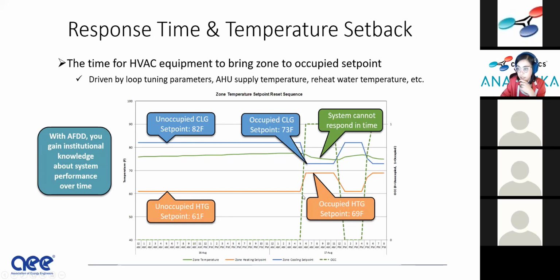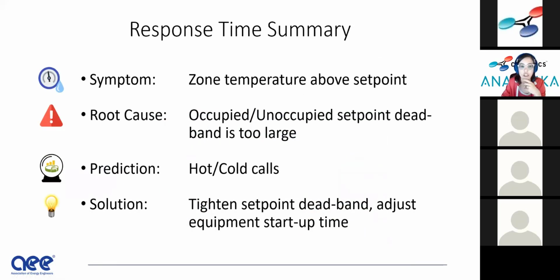Now, what we're trying to find is the response time of the space. How long does it take for the space to get to temperature in the morning to make it to set point? The answer is this room couldn't possibly get to temperature in time. You can see it cannot respond in time in the 10 hours or so that it's occupied. So we can help give customers that information that the symptom here is that zone temperature set point wasn't being maintained. And people might say, gosh, why is that?